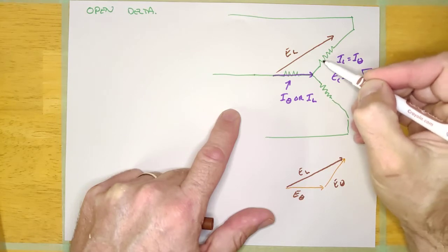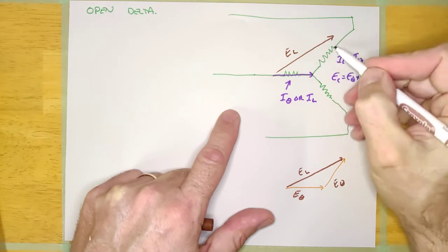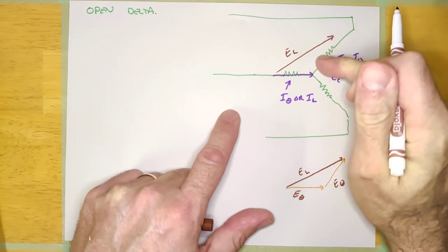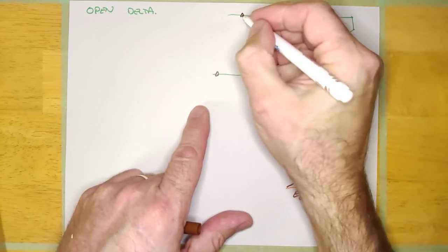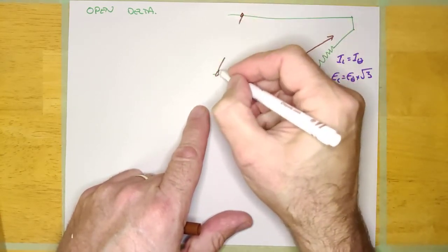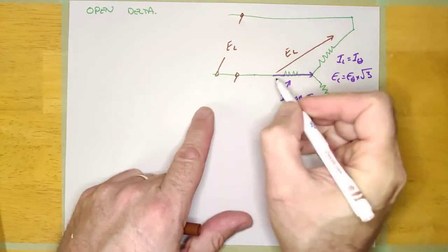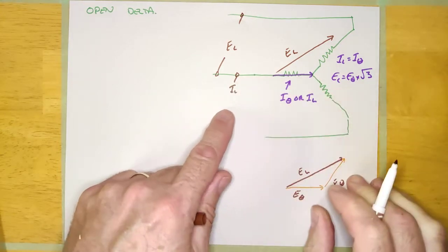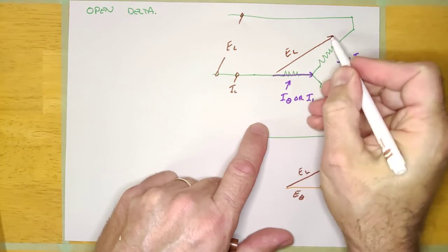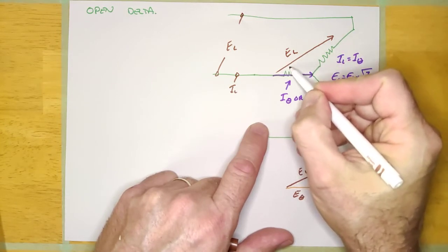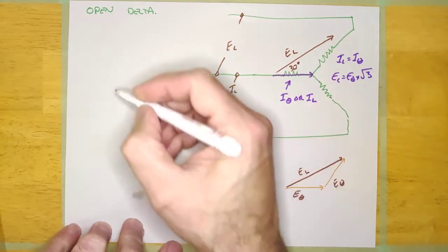And I'm drawing all this stuff here so that you know that even though this is a resistive load, and a resistive load causes the voltage and the current to be in phase in the load, and they would be, okay? If I scope the voltage from here to here on a scope, E line, and I scope the current right here from this load, I line, if I took a look at those on an oscilloscope, guys, I would see that there is an actual 30-degree phase angle difference between the line voltage and the line current.